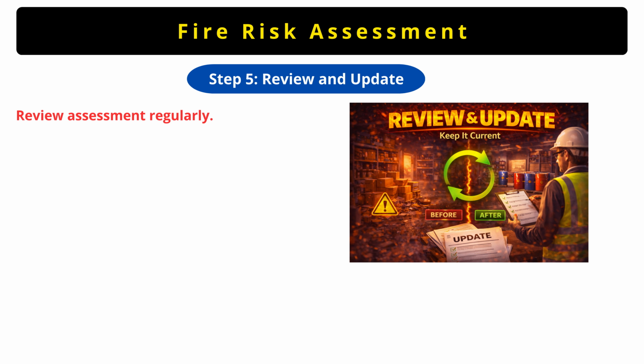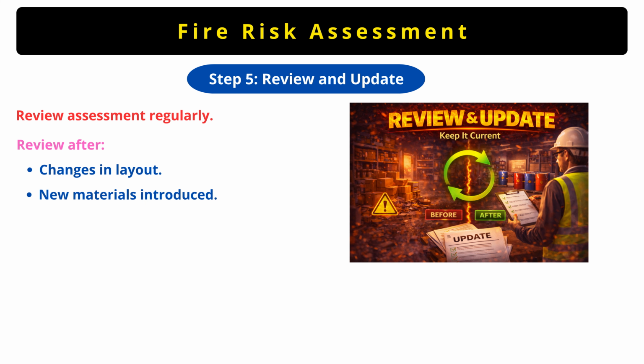Fire risk assessment is not something you do once and forget. It must be reviewed and updated regularly. Now the question is, when should we review it? When there is a change in site layout, when new materials are introduced, when a fire incident occurs, and in those situations you should review your risk assessment.